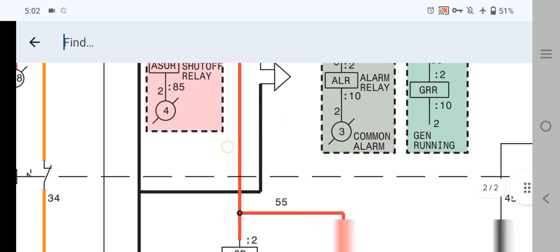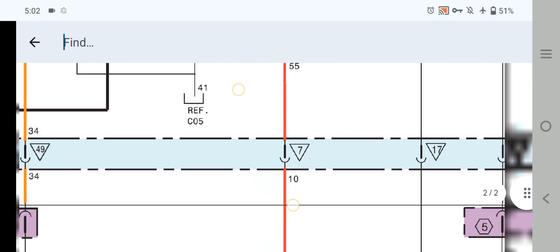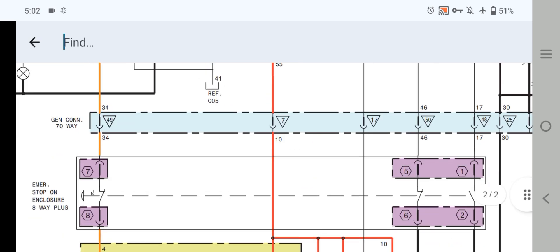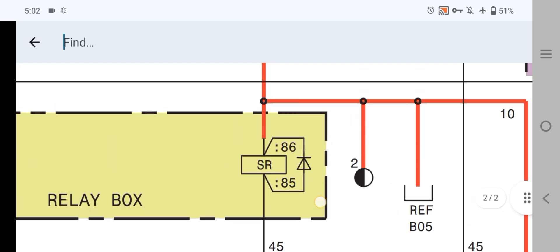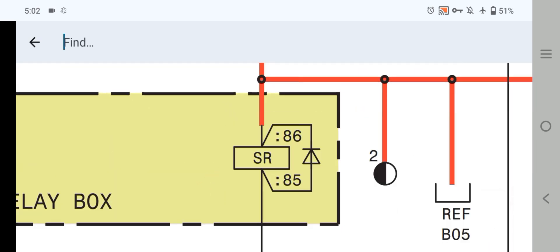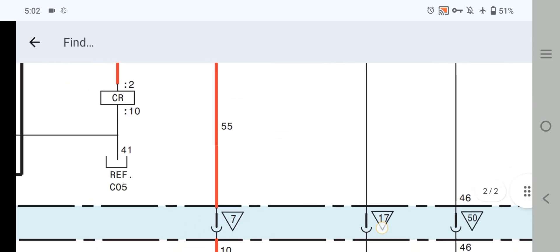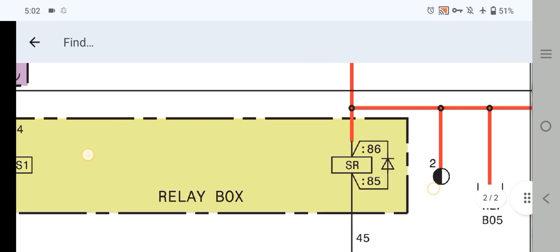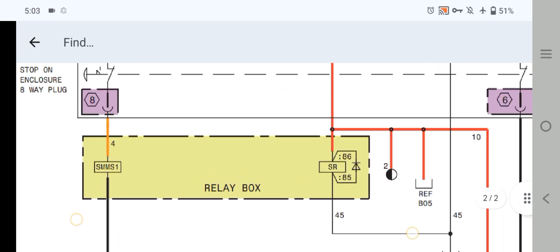The battery positive is directly fitted to all relays — also to the fuel relay and to the start relay. As you can see, this is the generator 70-way connector. The start relay has pin 86 and pin 85 — pin 85 is ground and pin 86 receives the battery positive signal from the EMCP 4.1 and 4.2 controller to energize the relay. When the engine goes to start and cranks over, this completes the starting circuitry.